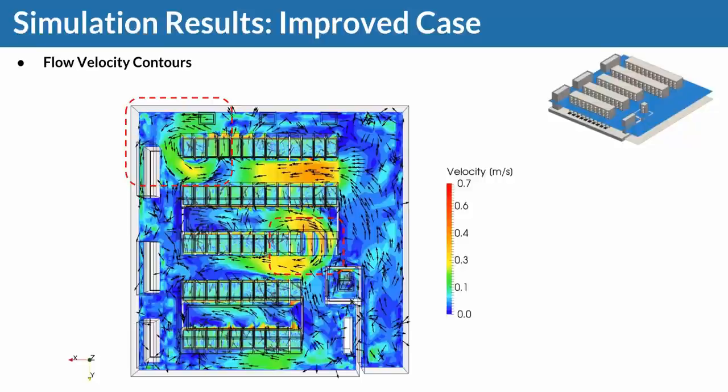On the other hand, if we look at the third and fourth row of servers, we had two racks that were empty and did not have any servers in them, or for example, they had non-working servers, with significant space allowed. This will allow significant air recirculation to happen from the hot aisle outwards to the cold aisle between the second and the third rack, if we come from the bottom, and will significantly reduce the performance of our system.